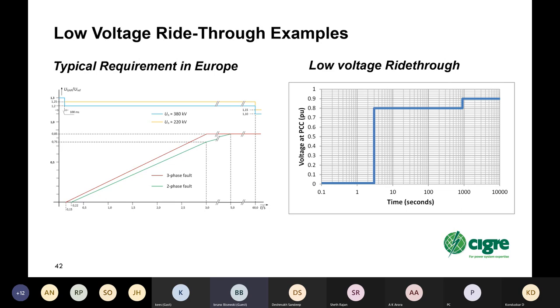And here are some typical low voltage ride through examples. On the left is something that we've typically seen in specifications in Europe, and it derives from power withstand requirements for renewable generation, such as wind generation. But you might decide that you want something a little more severe, and you might require quite a long ride through requirement, such as something on the right where we've shown three seconds at zero voltage followed by 80% voltage for quite a long period of time, 900 seconds, and followed by continuous at 90%, and that has been specified in some cases. But that depends on what your requirements are. Some of it costs money, and so you should be careful to specify what you need and not over-specify it.